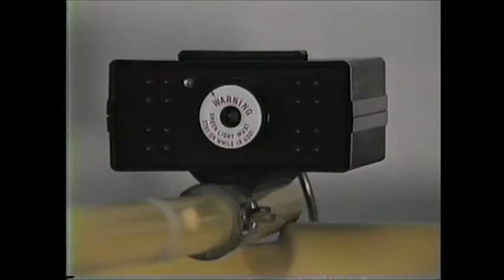The audio indicator operates simultaneously with the first bank of lights. The unit is calibrated for line-to-ground voltages of 600, 2,000, 7,000, and 11,000 volts. The banks of lights flash alternately so that it is easier to distinguish the number operating from a distance.